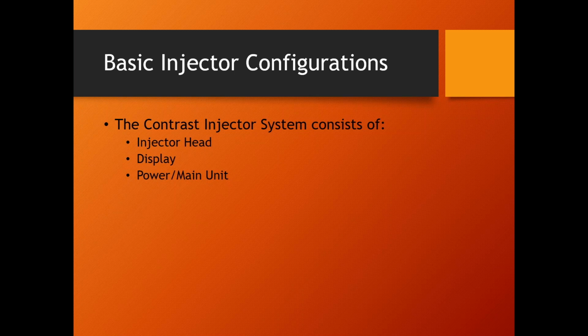When you're talking about doing the PM, typically a PM for a contrast injector, depending on the model, a full PM doing everything the way you're supposed to can take anywhere from 45 minutes to an hour. There's a lot of cleaning that takes place when you're doing contrast injectors. There's one injector model, called the Provis. It's still very common. It is end of life, but there are still tens of thousands of them out there. That one takes about 2 hours because it's an older system and has tons of things to do to it, whereas newer contrast injectors don't need any of those things. So the Provis will take an hour and a half to 2 hours, depending on how experienced you are and how much cleaning is necessary. But for the most part, it's an hour or so.